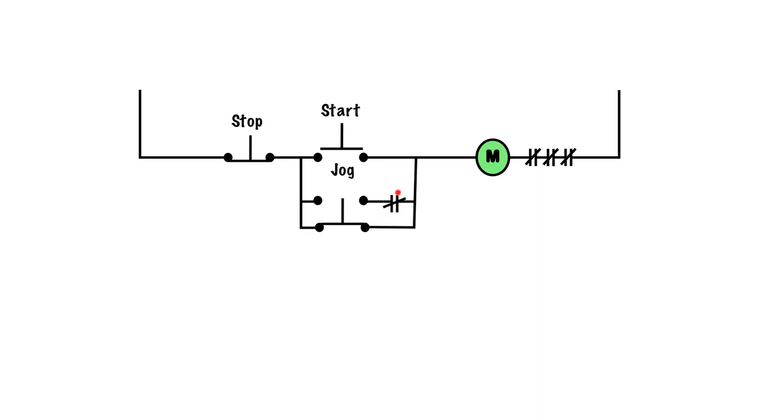So energized, closed. However, it won't hold in because it gets to this point here and it's opened up with this switch, with this push button, which seems pretty ingenious and typically it will work. Judging here, if we let go of the button and I'm in the halfway point here, I've broken the circuit which will in turn de-energize this M coil which will open up these contacts.